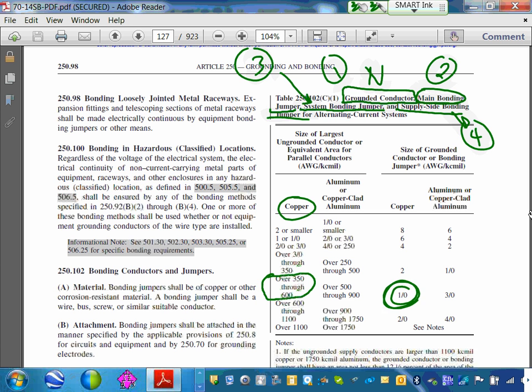So what's your minimum? What did we come up with before? 2 AWG. So you choose the largest. Oh, so that's your bare minimum. Shall be killed if you use less than that. Oof, that's harsh. Shall be jailed. You see what I mean? This is the bare minimum that you can't go below. So if we got smaller than 1/0, we'd have to go with 1/0 regardless of what you came up with. That's the bare minimum. Am I clear about this? Very clear. The bare minimum.